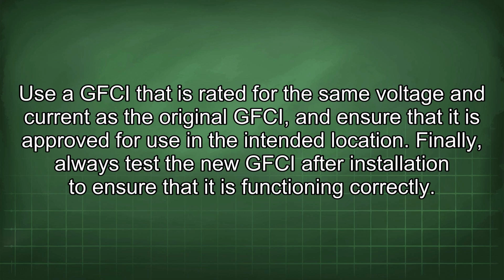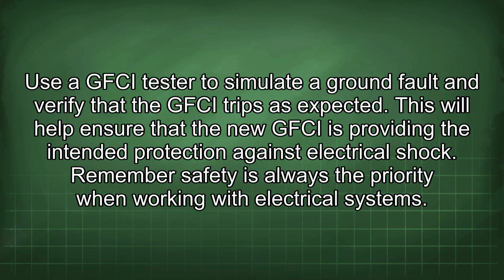Finally, always test the new GFCI after installation to ensure that it is functioning correctly. Use a GFCI tester to simulate the ground fault and verify that the GFCI trips as expected. This will help ensure that the new GFCI is providing the intended protection against electrical shock.